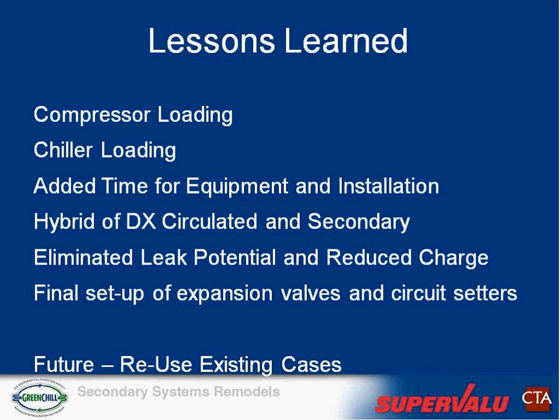And then the controls and the field folks looked at cases with solenoids that were cycling a lot, and closed down some of the circuit setters so they had a longer run time and really smoothed that out. The feedback I've got from those involved is that these systems now are running very smooth. Product temperature is very stable, and it's just been successful.